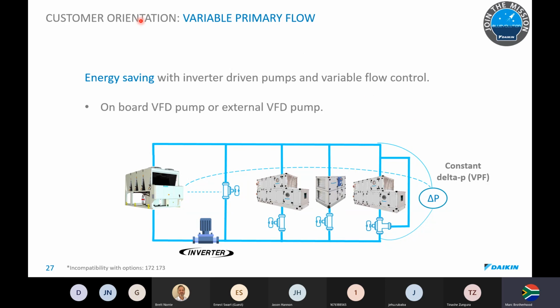The variable primary flow design that this chiller also has built in. So it's energy saving because we have inverter driven pumps as well as variable flow control. So your furthest unit would have a pressure sensor across it, and as the pressure drops across the chiller, it would send a voltage back to your PC board to tell this pump to slow down or speed up. So there's continued energy saving depending on how you parallel your loads within your primary loop circuit.